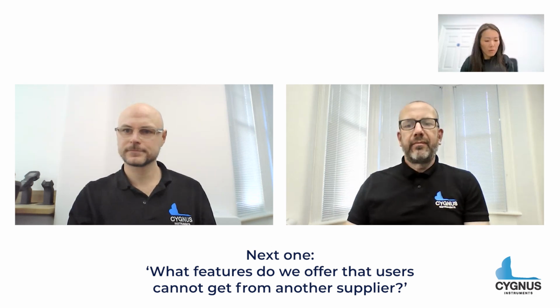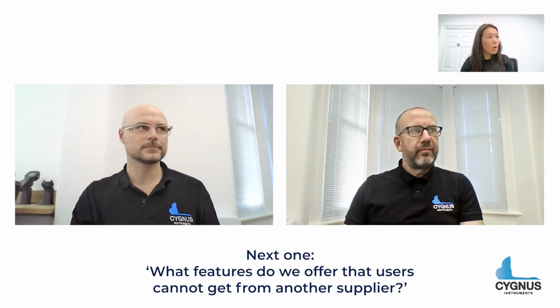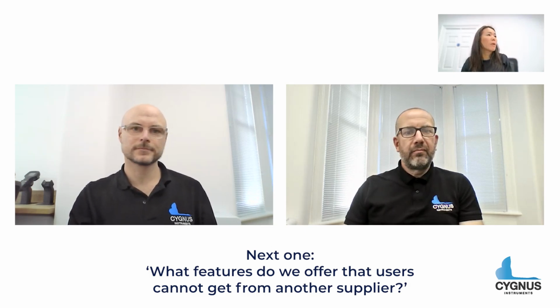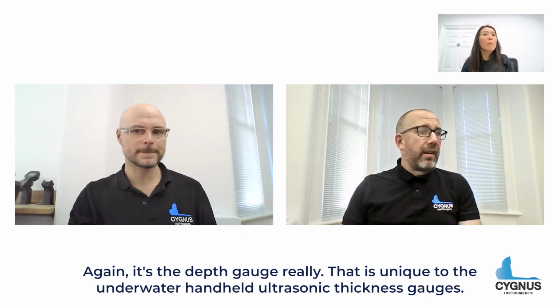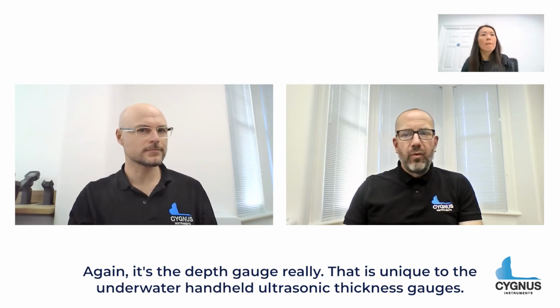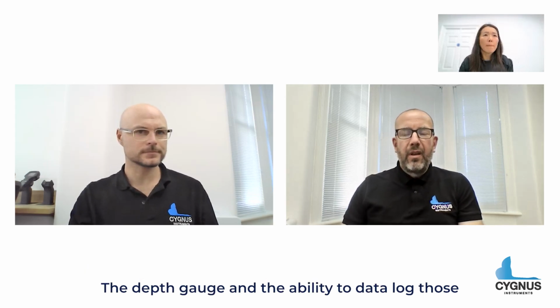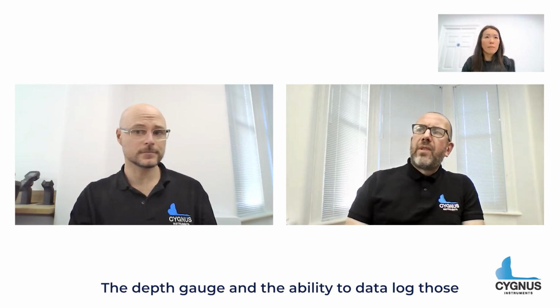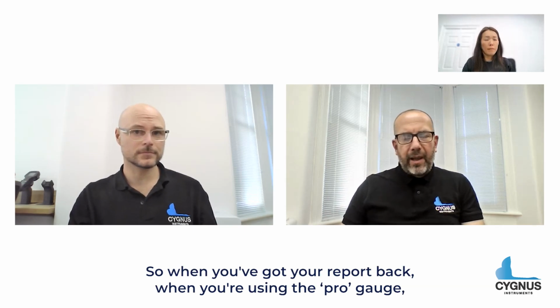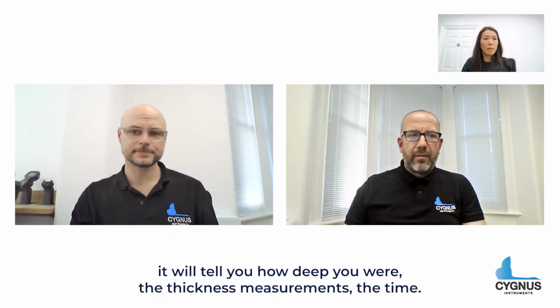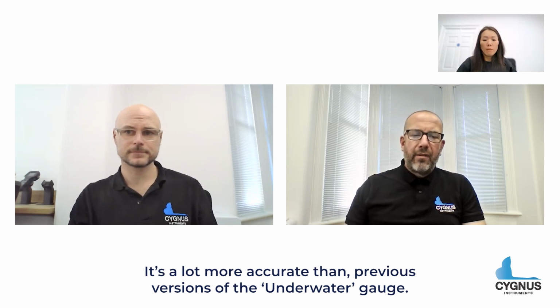See if there's any more questions. Okay, next one. What features do we offer that users cannot get from another supplier? Again, it's the depth gauge really. That is unique to the underwater handheld ultrasonic thickness gauges. The depth gauge and the ability to data log those. So when you get your report back when you're using the Pro gauge, it will tell you how deep you were, the thickness measurement, the time. It's a lot more accurate than previous versions of the underwater gauge.